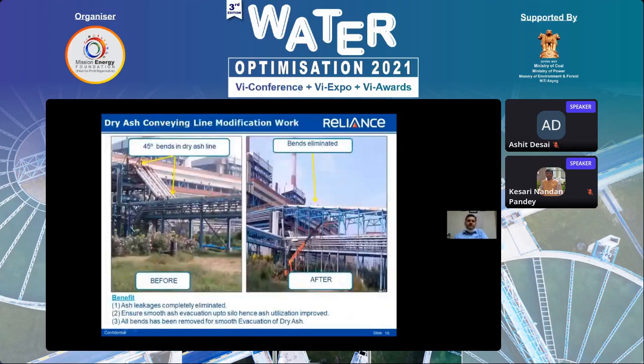These are the modifications. Initially, we had a lot of bends in our dry ash line from the ESP to the silo. The silo is 1.2 kilometers away from the ESP hopper, and you can see a lot of 45-degree bends. We have eliminated those and gone straight, so the ash glides from the ESP and goes to the silo without any hindrance. That was our philosophy, and it resulted in a lot of improvement, as you can see in the data also.